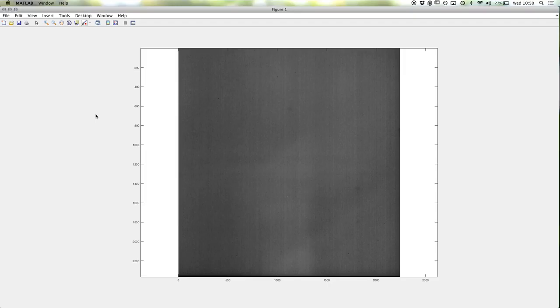This shading image is also taken as an average of 100 images with no object in the way, and we use it for calibrating for the empty space.